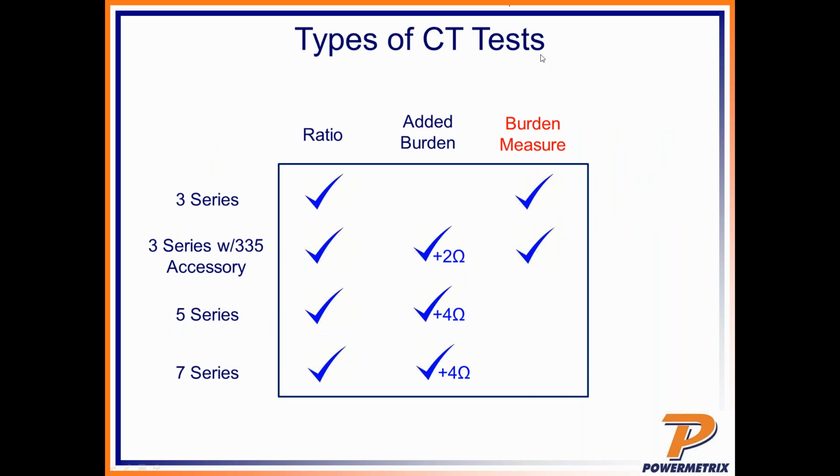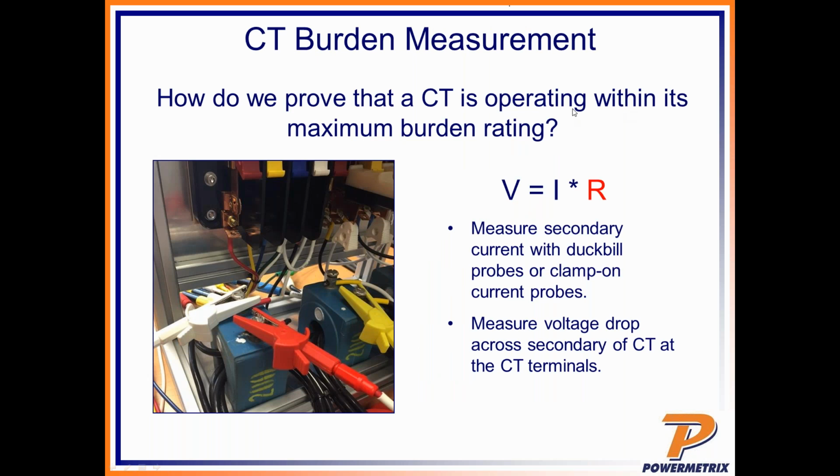Moving forward, our last type of CT test is the burden measurement, okay? And this is something that the 3 series does that I don't know of anything else in the industry that actually does. It's a really, really cool test. And what it does is we're actually measuring the burden on the CT, okay?